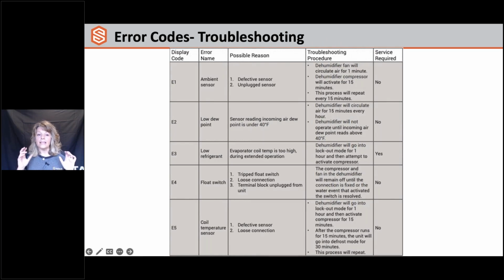So one of the things that we talked about on that display of the digital control are error codes. In our manual, you will see the different display codes for the errors. We have an ambient sensor, so if the air going into the unit is out of the range, we're not going to get dehumidification, and we provide you a troubleshooting procedure. The dehumidifier fan will circulate air for a minute to test that air. The compressor will activate for 15 minutes, and it's going to keep repeating this until the air is within that ambient sensor range.